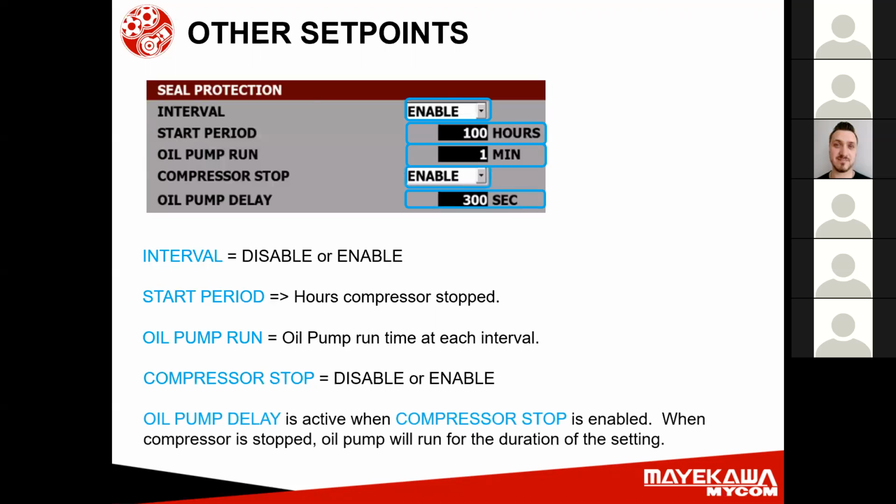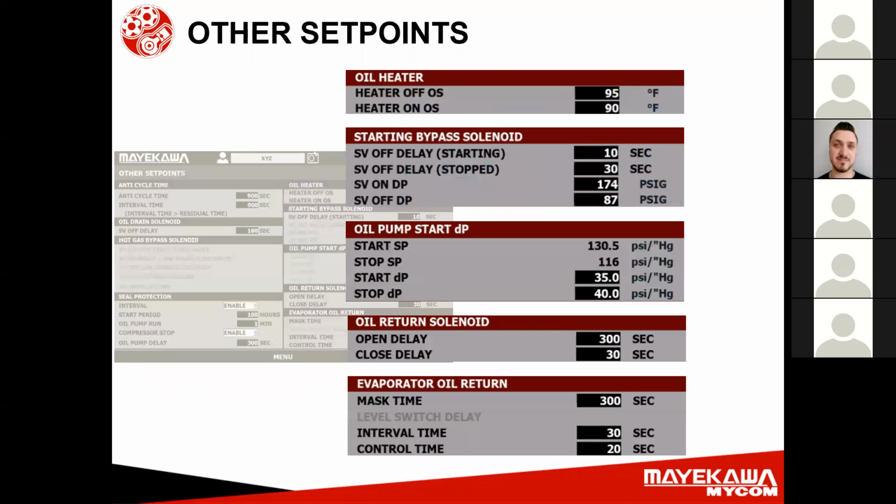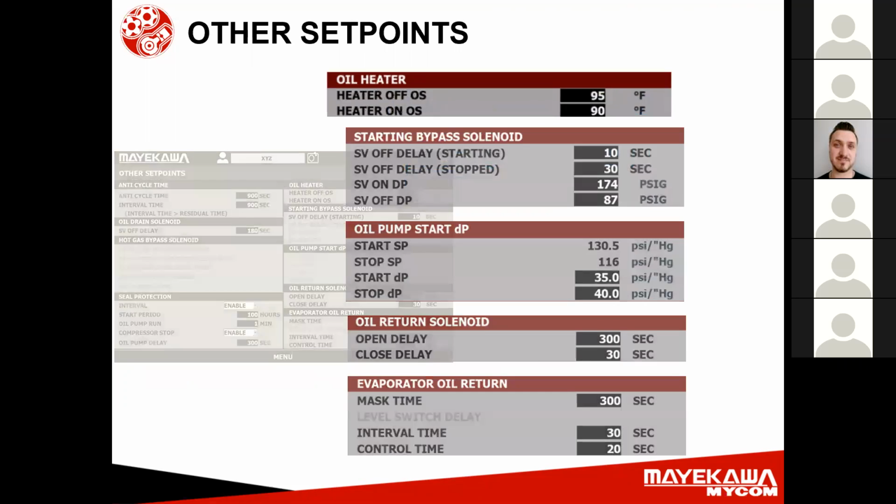Oil pump delay is active when compressor stop is enabled. When the compressor is stopped, the oil pump will run for the duration of the setting. Now let's take a look at the right side of other set points.